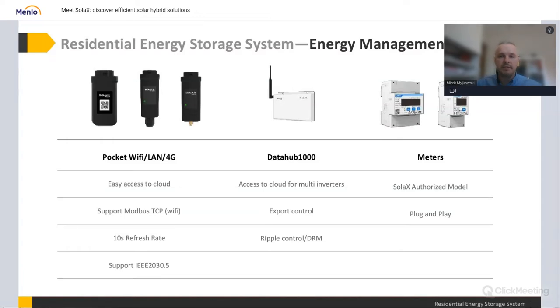But the most important thing here is also the meters, the metering devices. It can be a meter, or it can also be a current transformer. These are eyes and ears for the hybrid system. So without them, there is no hybrid. The hybrid doesn't know what to do, doesn't see where the house ends, doesn't know what concerns it, what it should supply from the batteries or not, because there has to be some kind of border between grid and house, and that border is called the measuring device, meter or CT, and it has to be installed exactly at the border between the grid and the house.